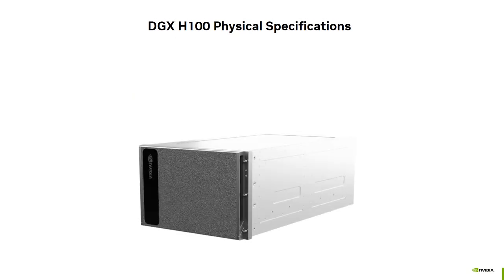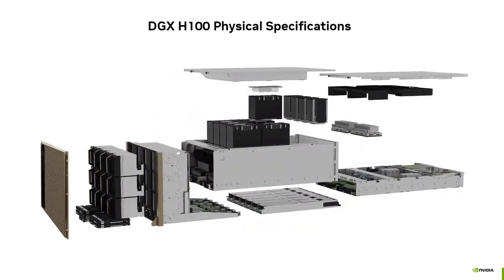Let's look at the physical specifications of the DGX H100 system. It is an 8-rack unit high chassis that fits in a standard 19-inch rack. The system is quite heavy and requires a mechanical lift to help get it out of the packaging and safely installed in a rack. The DGX H100 is physically constructed from a handful of modules, each handling discrete functions in the system. At the front, shown on the far left side, we have the gold bezel that should be familiar to anyone who has seen a DGX before.